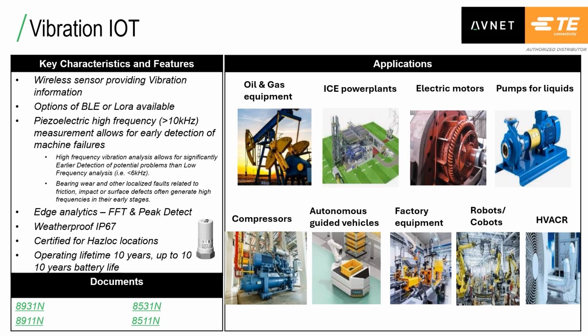The new TE8 series of wireless vibration sensors combines a piezoelectric accelerometer, frequency data analysis, and multiple wireless data transmission options combined into one compact battery-operated device that measures both vibration and temperature data. It was designed for harsh environments and is certified to work in hazardous locations. Some of the key characteristics and features of TE's wireless vibration sensors include options for either BLE or LoRa communication protocols, and a piezoelectric high-frequency sensing element that allows for early detection of machine failures.